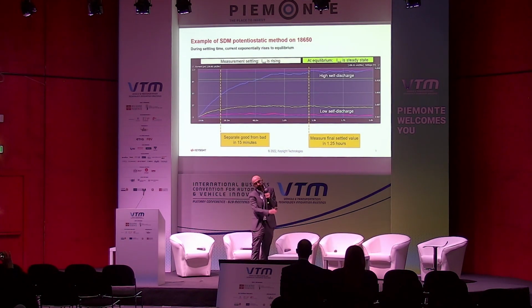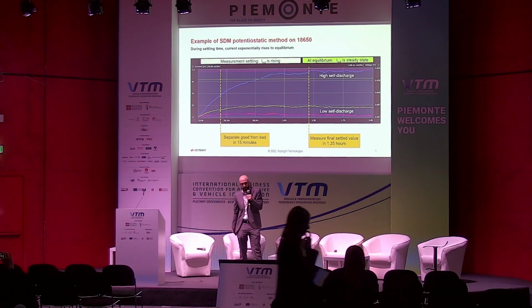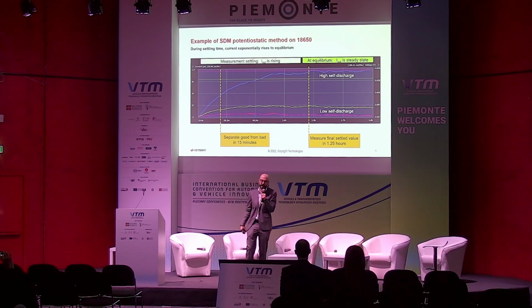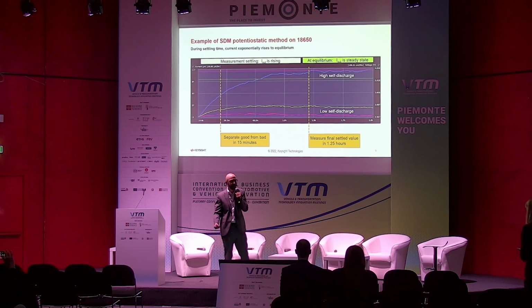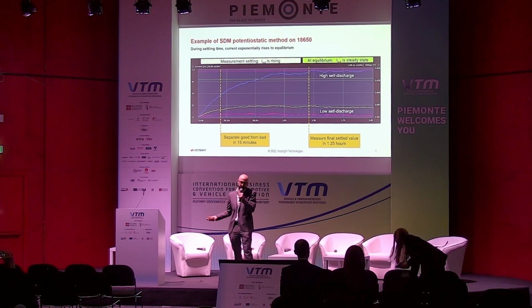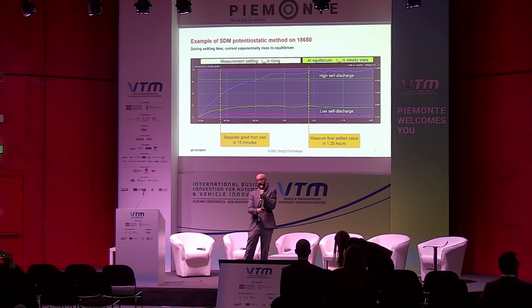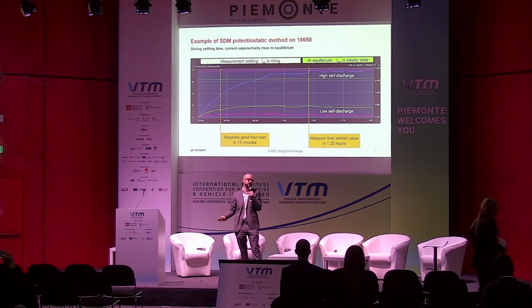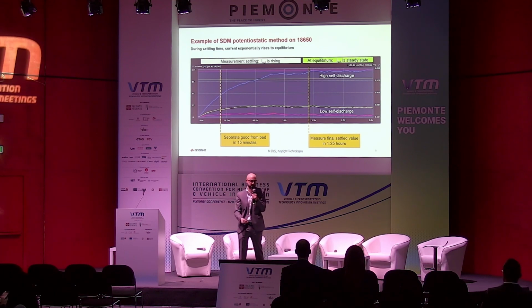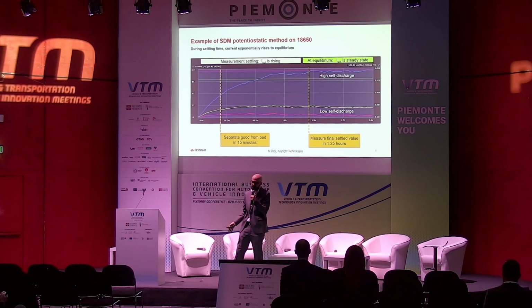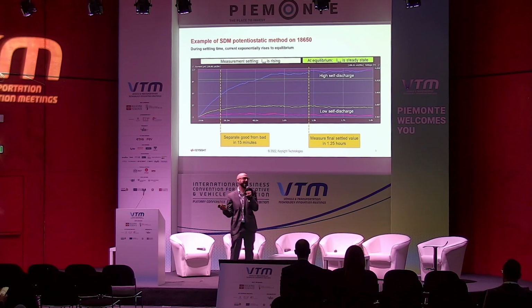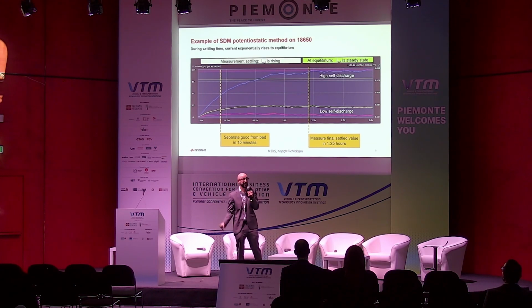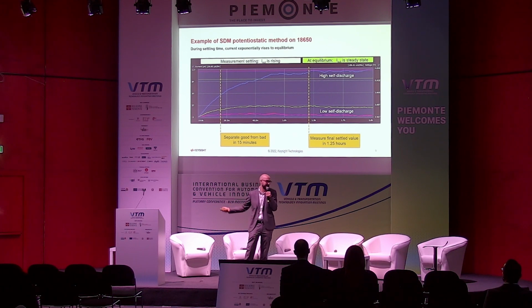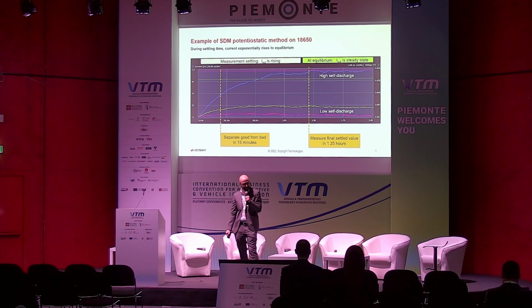So we can say for this kind of cell, which is an example, a test of the 18650 cell, within 15 minutes we are able to understand if the cell is good or if the cell is bad. And the stabilization of the process in this case happens after only 1 hour. So as you can see, it's stable, so you can make the measurement and then discriminate which is a good cell to go, for example, in the automotive environment, which is a bad one that can go for other applications or needs to be thrown away or recycled, I would say.